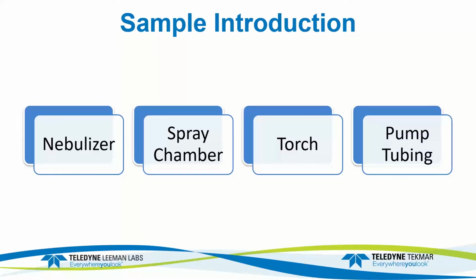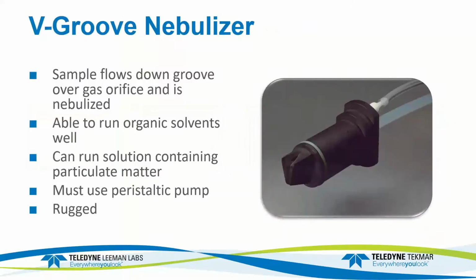We'll next just take a look at sample introduction. In that case, that consists of the nebulizer, the spray chamber, the torch, and the pump tubing. So this is for someone that may not be familiar with wear metals or analysis of organic type samples. This will just be a little bit of background for them, right? For oils application, we've always used the V-groove nebulizer, and so this nebulizer consists of a sample tube that delivers liquid onto a groove. Within the groove, there's a small hole which is located roughly right in this location.